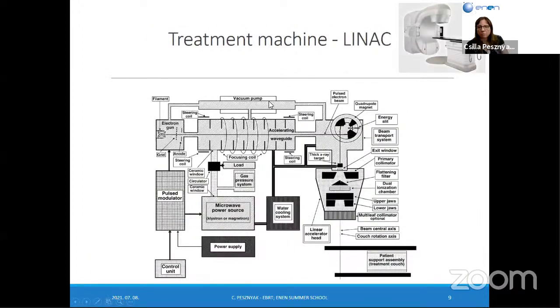Then here's the treatment machine construction for linear accelerators. We mostly use these linear accelerators. You can see the pictures here, and there are the basic elements of it. First, one of the most important, of course, is the electron gun with the accelerating waveguide. Here there always has to be a vacuum in the accelerator. For this reason we need a vacuum pump. Then here are the microwave power sources, a pulse modulator, gas system pressures for the moving.